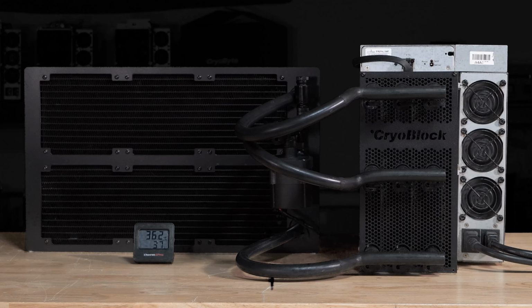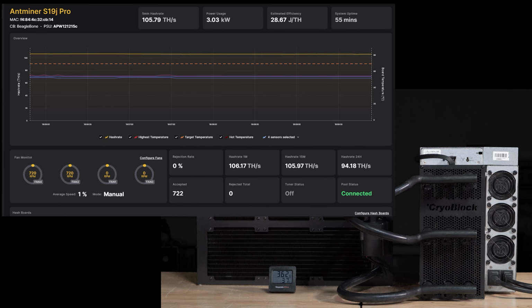Test 3 is balanced cooling. We jump in at the 55-minute mark and we'll fast forward to the end of the test. Our back cooling fans are running at 1% power, so almost all of the cooling in this test is being provided by the cryo blocks.